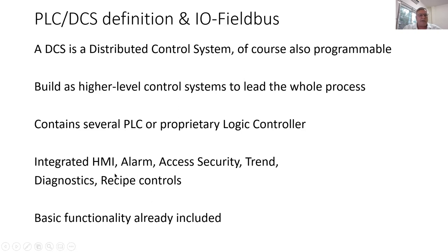So it has an integrated HMI. HMI means human machine interface. So the graphic displays and the operator graphic, they see what happens in the process. It has an alarm list and alarm support, even access security, so that not everybody can do everything on any parameter or on every equipment. We can have trends, that means historical data. We get diagnostics to see the health of this DCS, not only the controller, also up or down to the sensors and actors, but that we will see later at I/O.